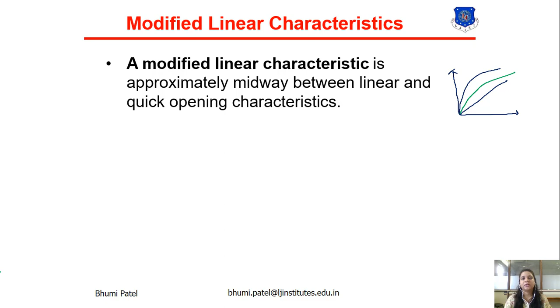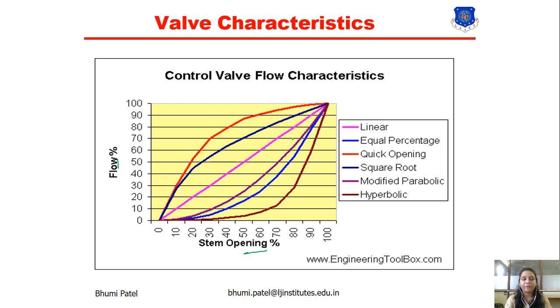Now, valve characteristic for the control valve. This is the total flow characteristic of the control valve, stem opening percentage versus flow percentage. Here this is the linear, blue color is equal percentage and red color is quick opening. This is the basic characteristic of the control valve. Now here you can see that the purple color indicates the modified parabolic, and the dark blue indicates the square root, which is also known as the modified linear, and the brown color indicates the hyperbolic characteristic. So this is the control valve total flow characteristic for the different applications.